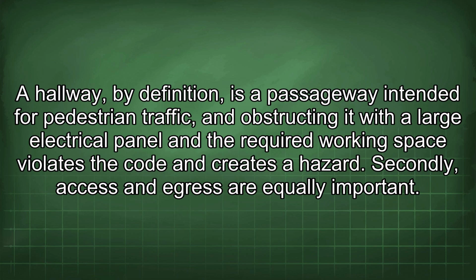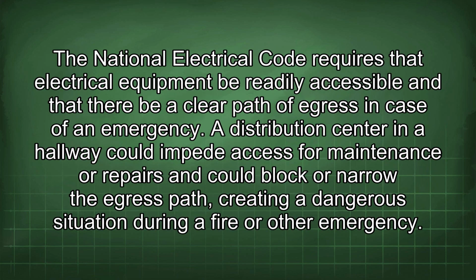Secondly, access and egress are equally important. The National Electrical Code requires that electrical equipment be readily accessible and that there be a clear path of egress in case of an emergency. A distribution center in a hallway could impede access for maintenance or repairs and could block or narrow the egress path, creating a dangerous situation during a fire or other emergency.